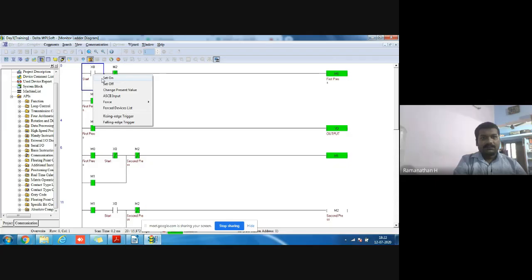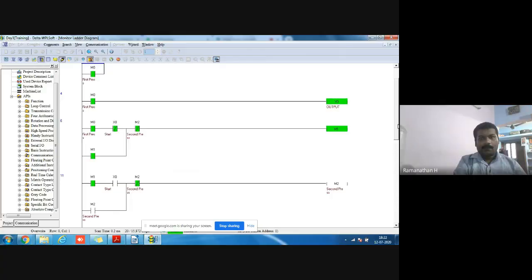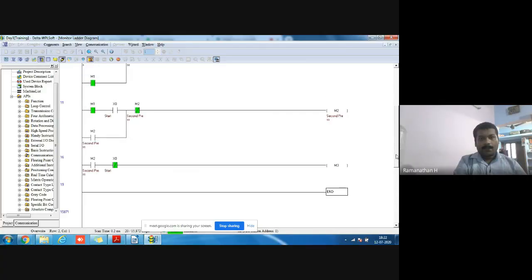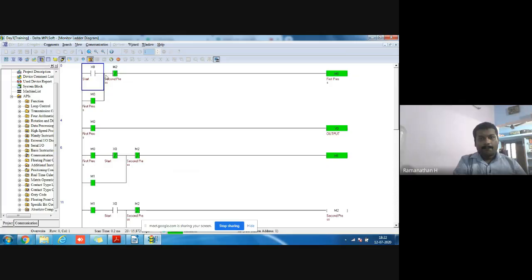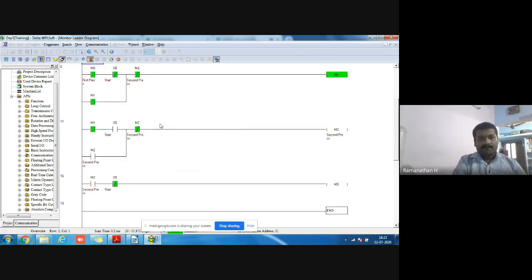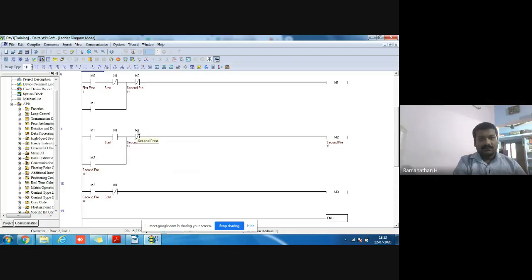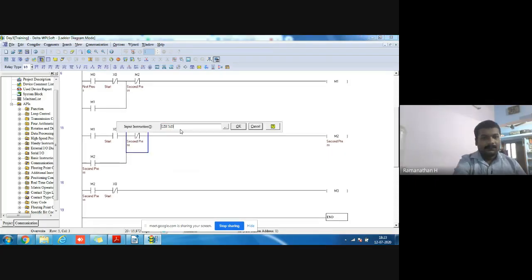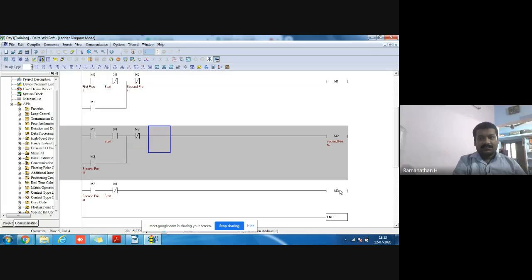I give the second press, release it. Yeah, here we made one mistake. It was M3. We interlock M3 to M2, M2 to M1 and M0. Okay, now again.